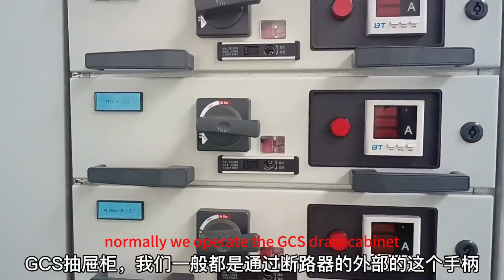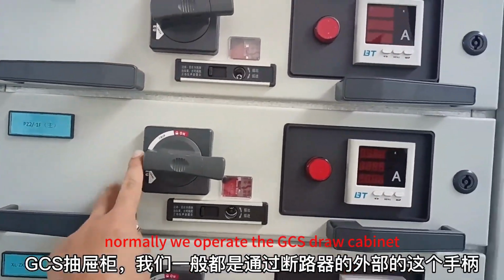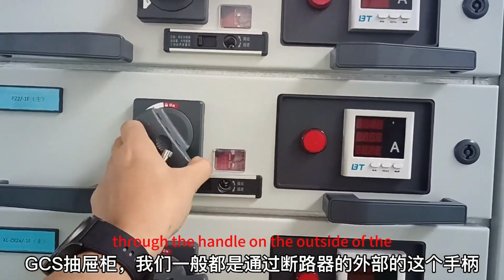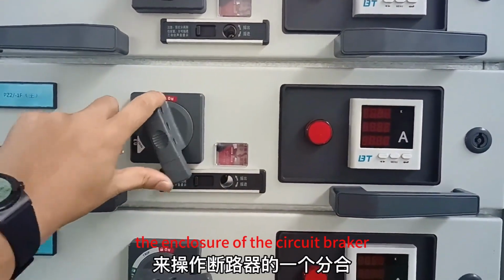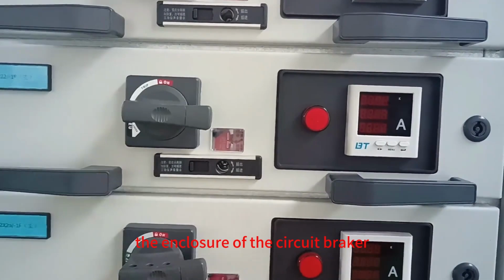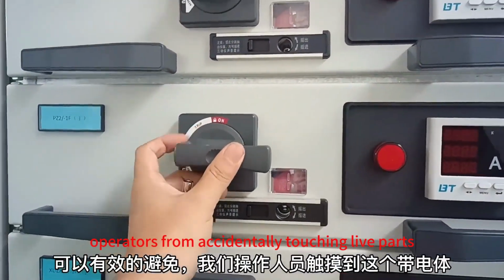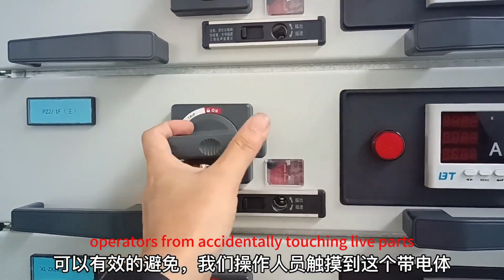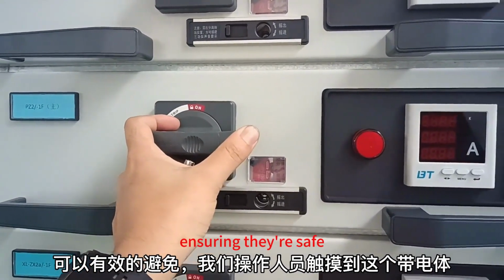Normally, we operate the GCS drawer cabinet through the handle on the outside of the circuit breaker. The enclosure of the circuit breaker effectively prevents operators from accidentally touching live parts, ensuring they're safe.